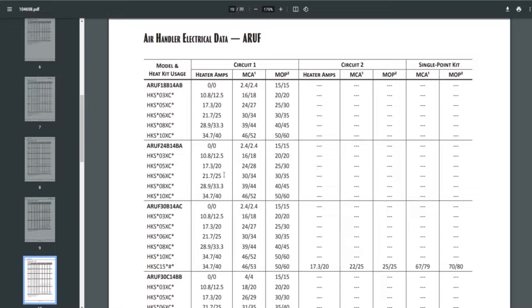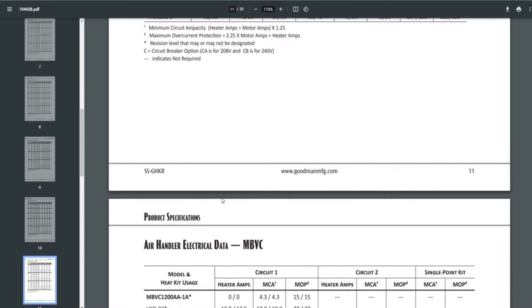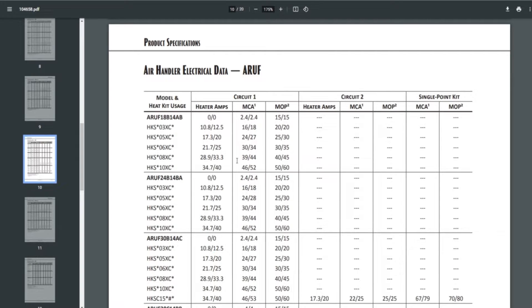Scrolling down to the ARUF 60, it supports all the way from 3KW to 25KW. Going back to the ARUF 18, you can see models HKS 03, HKS 05, HKS 06, HKS 08, and HKS 10. These smaller heaters (3KW to 10KW) have only one circuit. The first column shows heater amps — two different numbers because the air handler can run on 208V or 240V.